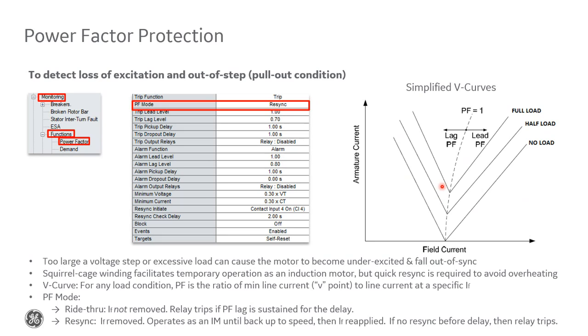Since the excitation either way affects the stator and field current, which in turn affects the power factor, we can monitor the power factor to detect any sort of a pullout condition. We would want to operate if the power factor falls too far to the left here in the lagging direction. So the power factor monitoring function in 869 is very similar to what we had in the SPM, but we added an additional setting for the power factor mode.